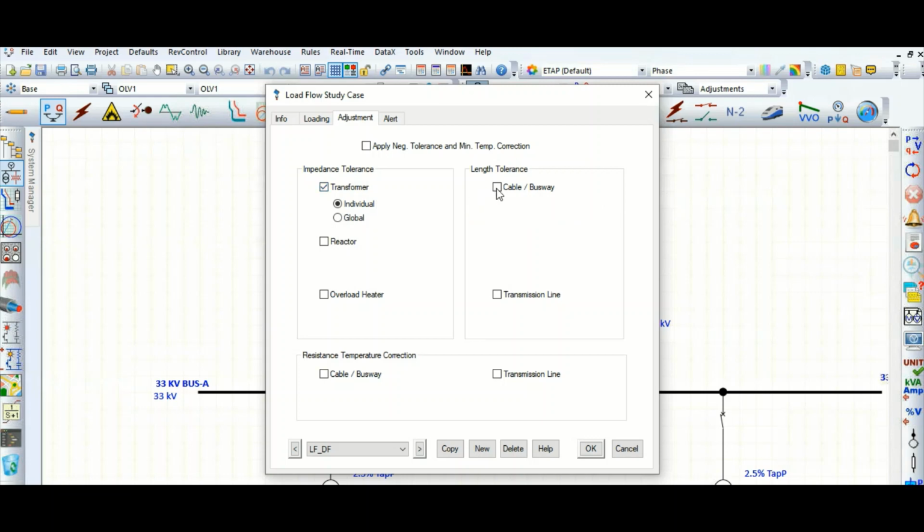Length tolerance you can consider if it is a greenfield project or a new project you are going to design. Otherwise, if it is as-built or an existing cable and the plant is running, you know the exact cable length and as-built cable details, so there is no need to consider any tolerance in that case. Or the transmission line. And here is the temperature correction for cable or busway, you can consider it also, you may or may not.